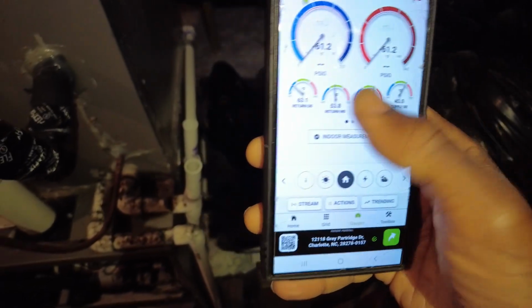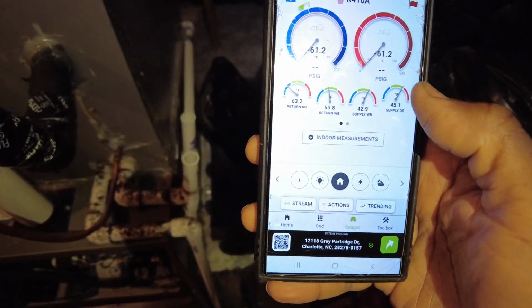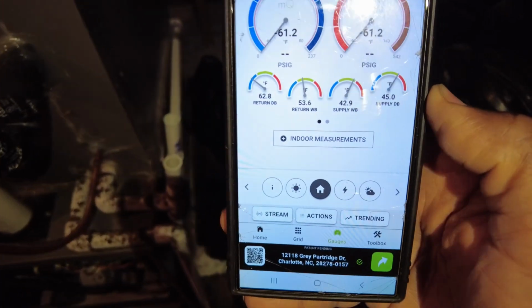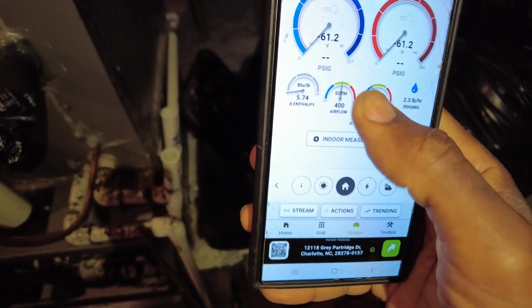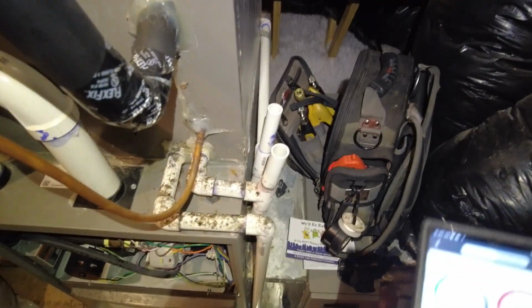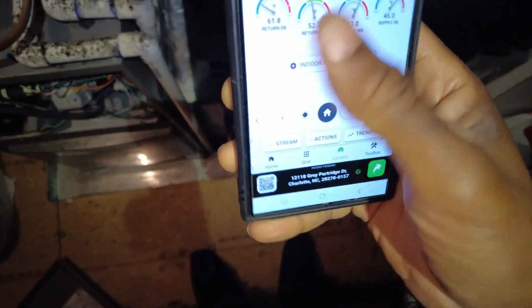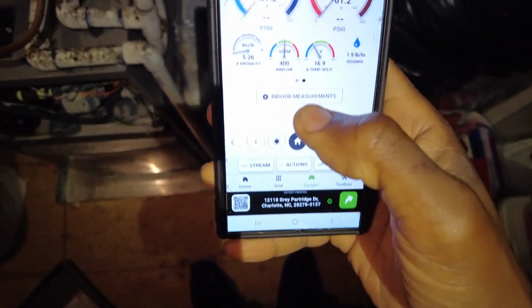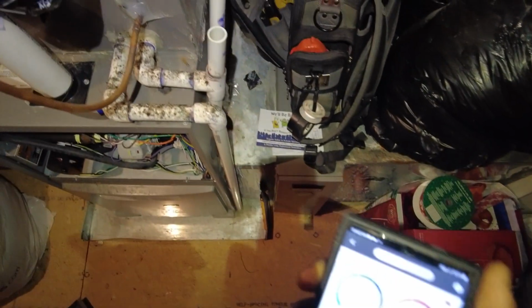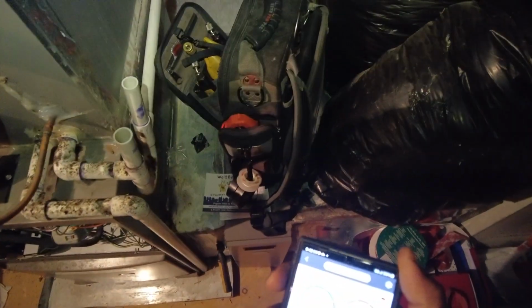And it was worse than that a second ago before I opened the second zone. It was like 50 something. The return was like 50 degrees. I had like a 10 degree split. So when I opened that second zone, it actually helped a bit, even though it didn't really close much more, that zone. So what's happening is basically it's recycling this air back through to return this really cold air, and it's just causing way too low of a supply temperature.